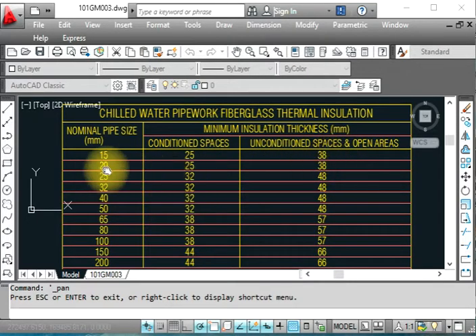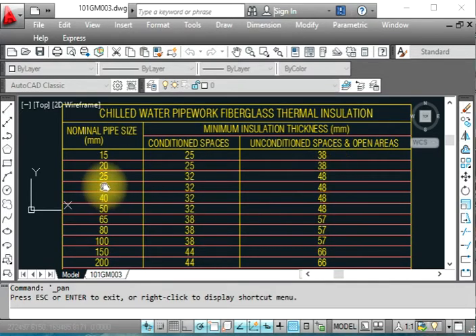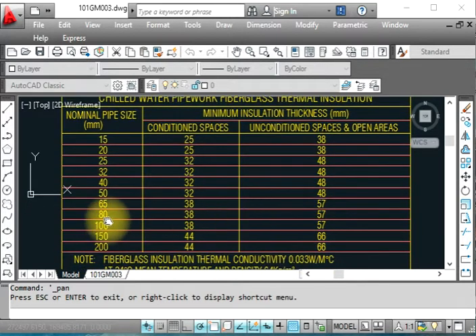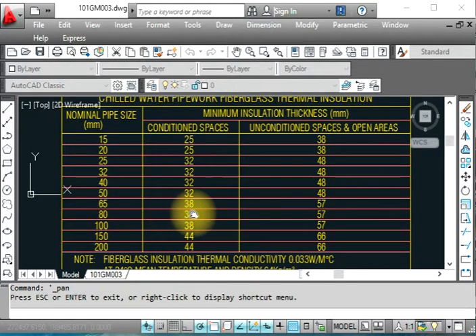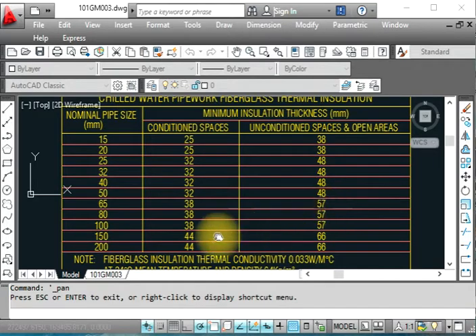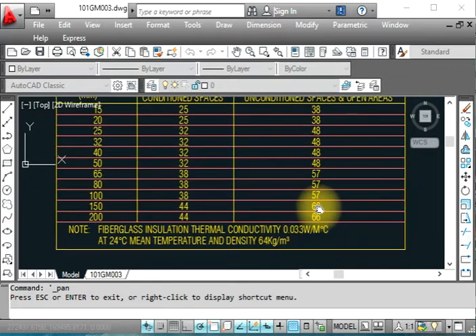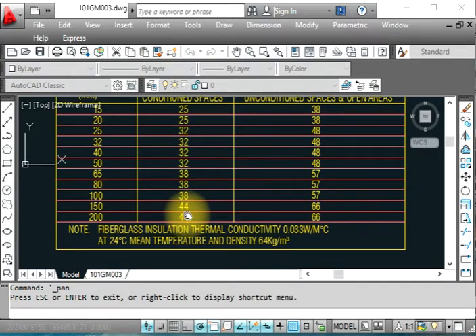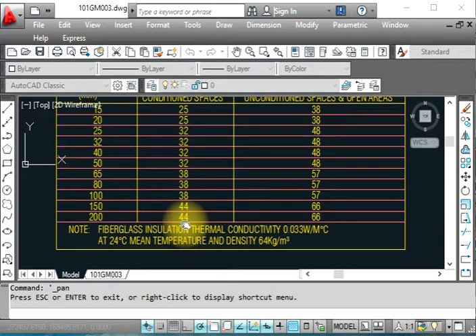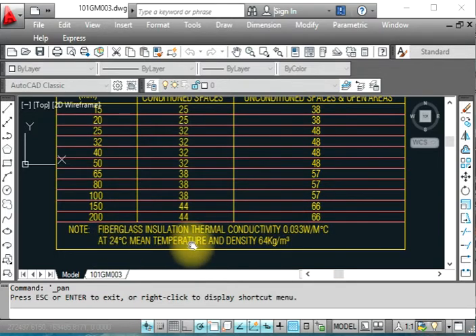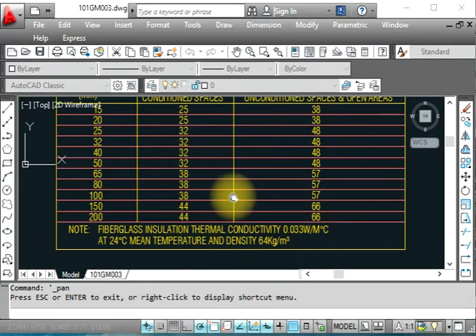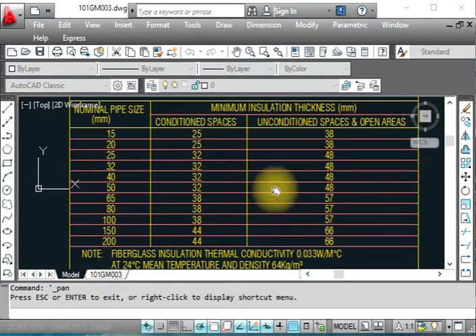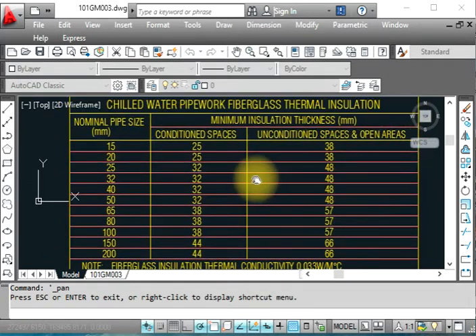For 20 mm pipe: 25 mm conditioned, 38 mm unconditioned. For 25 mm and 32 mm pipe: 32 and 48 mm respectively. For 40 mm pipe: same 32 and 48. Up to 65 mm pipe diameter: 38 and 57 mm. Up to 100 mm: 38 and 57 mm. For 150 mm diameter: 44 and 66 mm thickness. For 200 mm diameter: 44 and 66 mm fiberglass insulation. This follows thermal conductivity, temperature, and density specifications as per SMACNA and international standards.